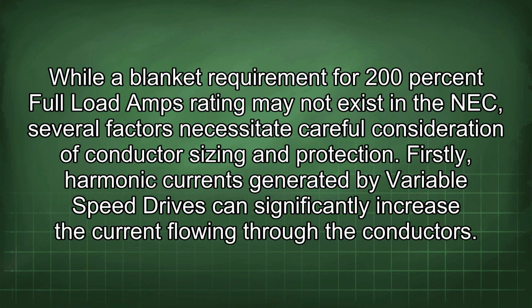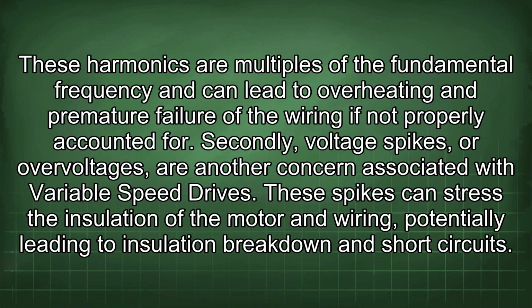While a blanket requirement for 200% full load amps rating may not exist in the NEC, several factors necessitate careful consideration of conductor sizing and protection. Firstly, harmonic currents generated by variable speed drives can significantly increase the current flowing through the conductors. These harmonics are multiples of the fundamental frequency and can lead to overheating and premature failure of the wiring if not properly accounted for. Secondly, voltage spikes, or overvoltages, are another concern associated with variable speed drives. These spikes can stress the insulation of the motor and wiring, potentially leading to insulation breakdown and short circuits.